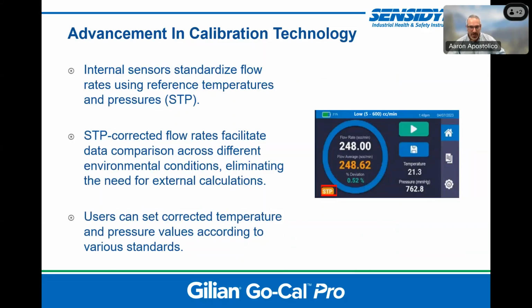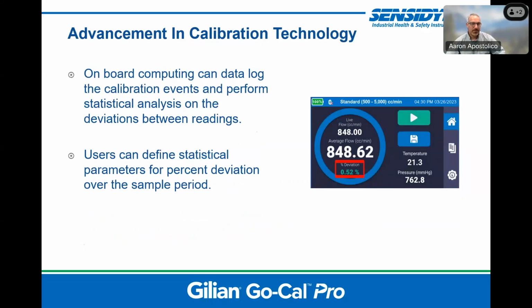Internal sensors within the unit allow you to convert to a reference temperature and a reference pressure to get an STP volumetric flow rate. Now that STP flow rate corrects the volumetric flow rate to an STP corrected flow rate. And this can be used to facilitate data comparisons across different environmental conditions, eliminating the need for external calculators. So the calculation uses the combined gas law to equate your ambient temperature and pressure to a reference temperature and pressure, holding everything else equal. Now, users can set that corrected temperature and pressure according to the values of the various standards, whether that's an STP that's recognized locally or an NTP value.